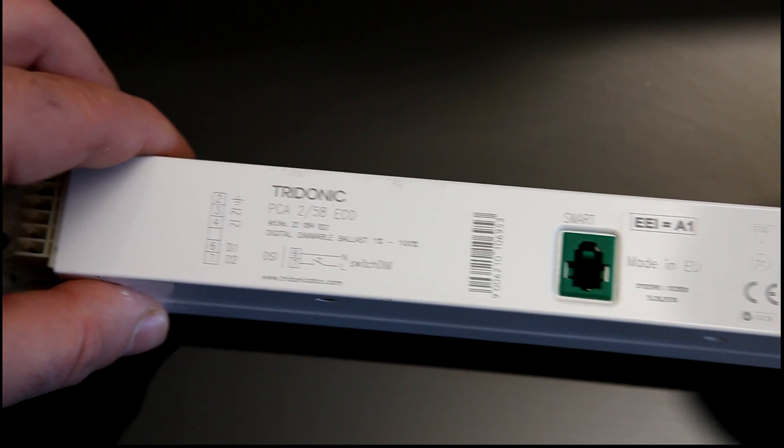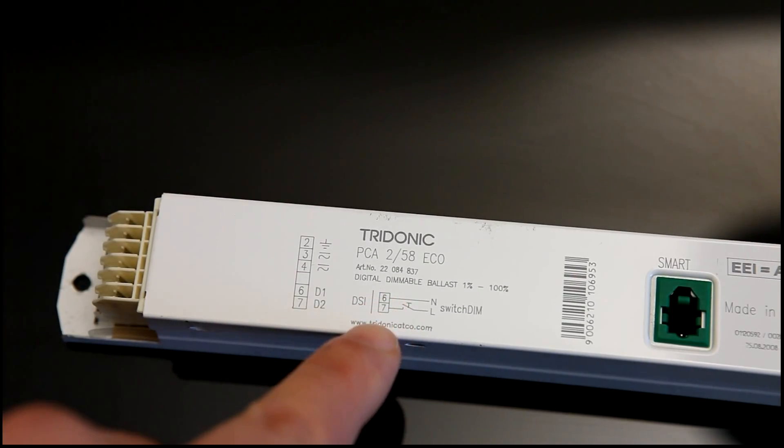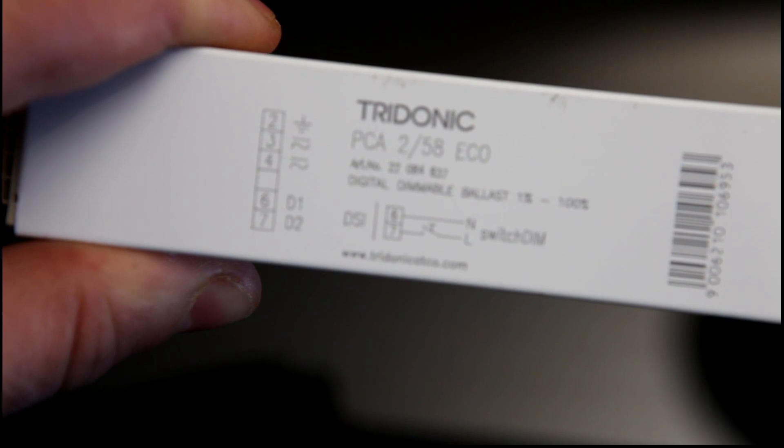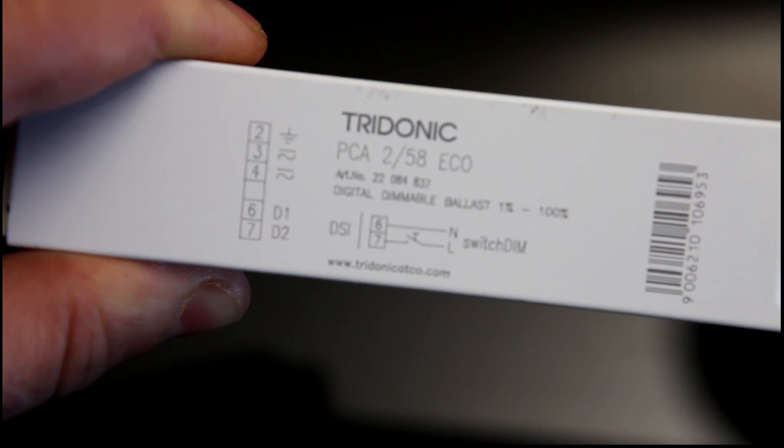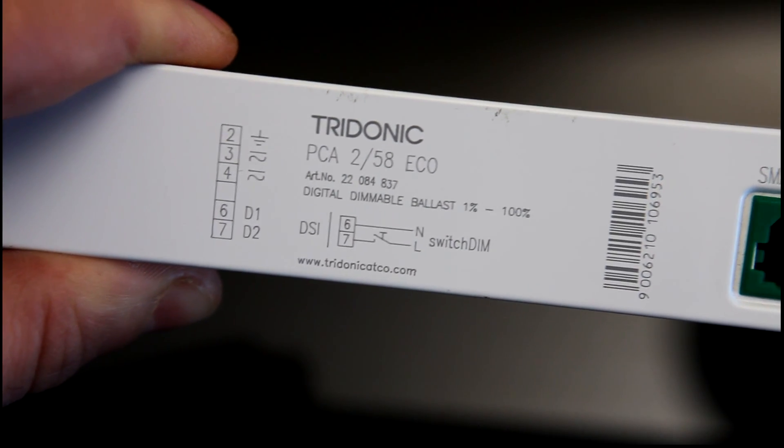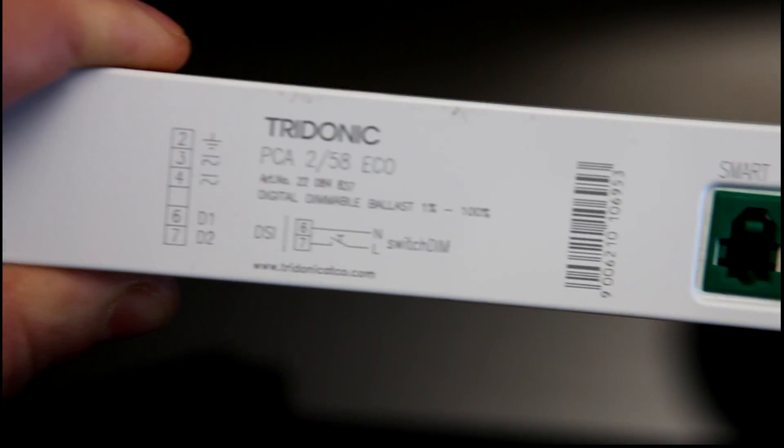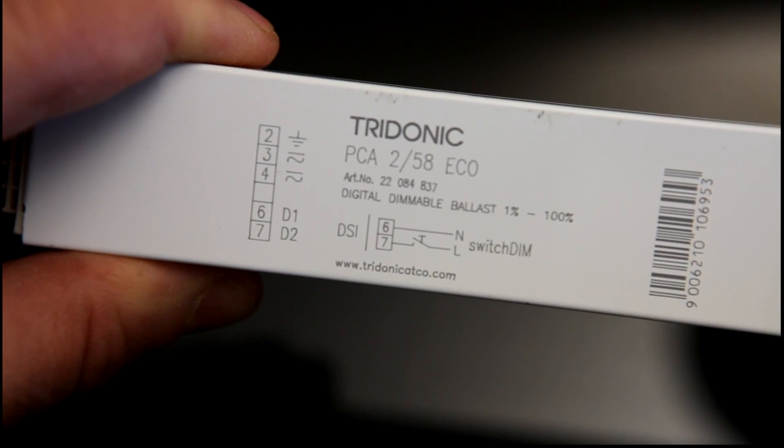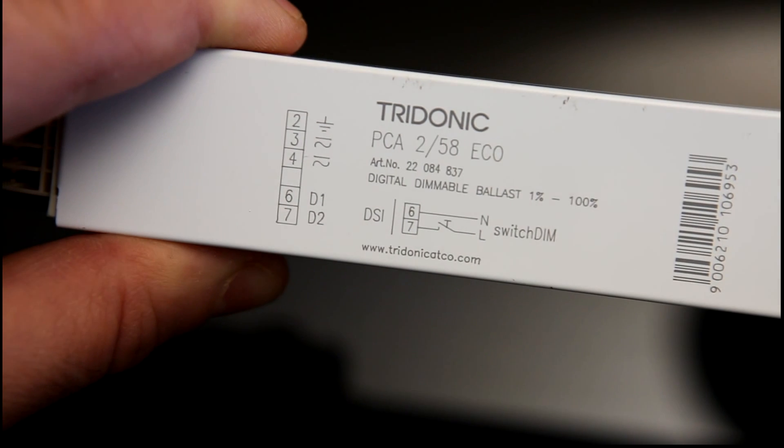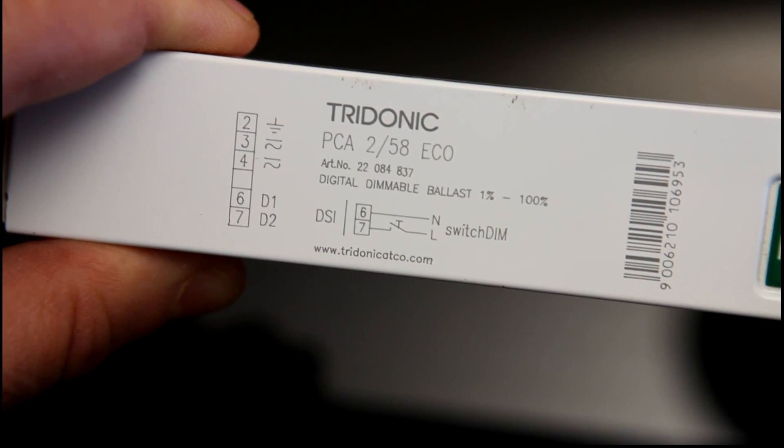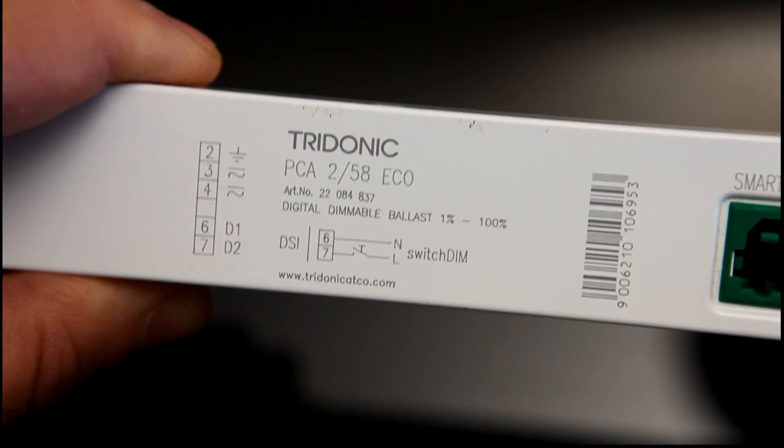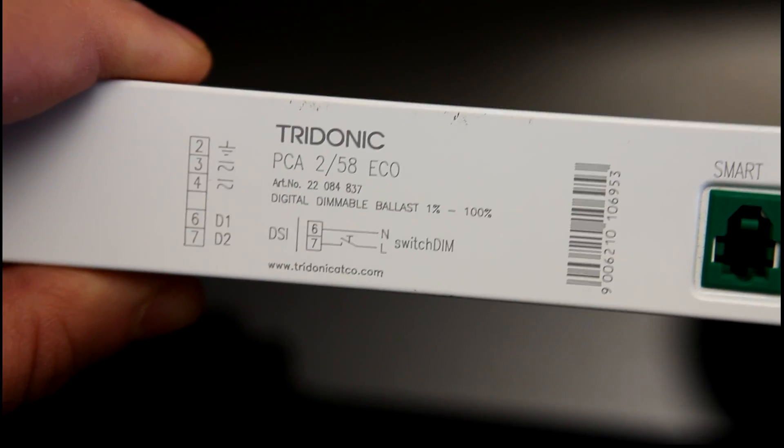Now, this is what's called a switch dimming ballast. This, rather than taking an analogue input, just simply takes a momentary push switch input. You simply short two terminals together, and the ballast responds by switching on or off in the event of a press, or dimming up or down in the event of a long hold.